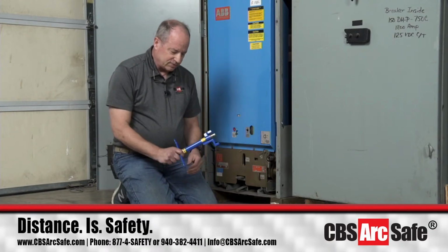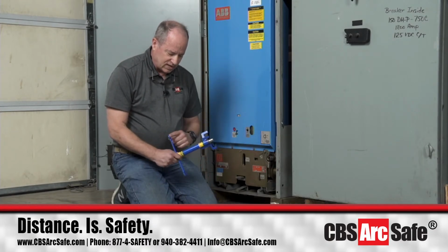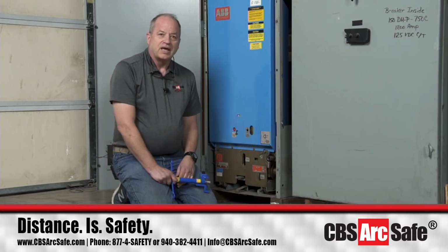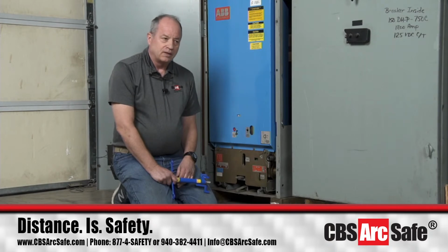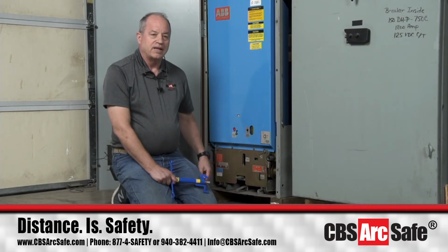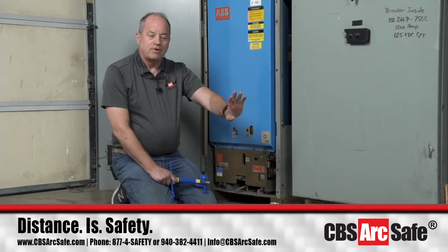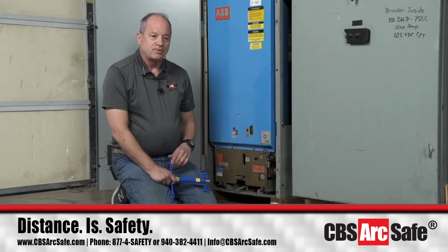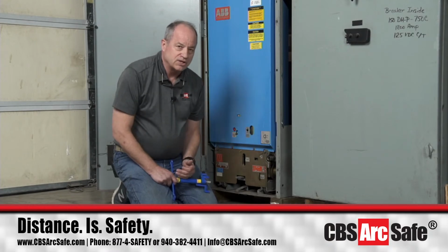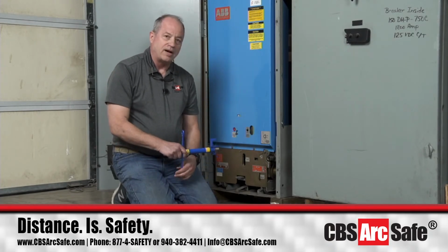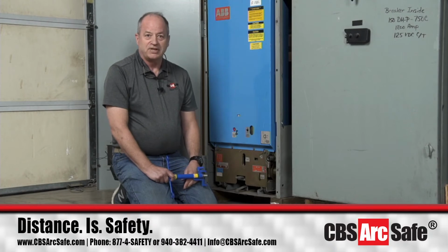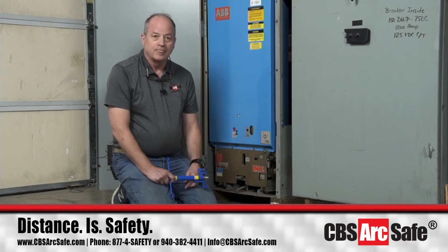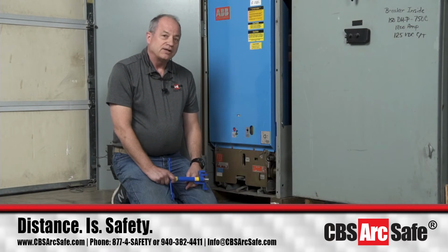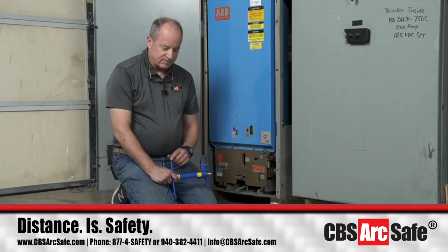You'll notice a couple things peculiar about this: a ring on the top and a ring on the bottom. That's because if you're operating the interlock manually, say the switchgear is all the way down on the far right side, I can't stand there and be outside the arc flash hazard boundary. So I have to pull from the bottom using a manual defeat with the leash. If I've got the interlock defeat control on my RRS-1, I can use it to defeat the interlock and hook it up here on top.